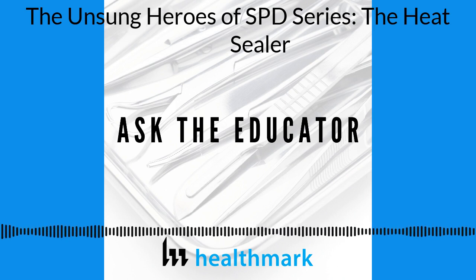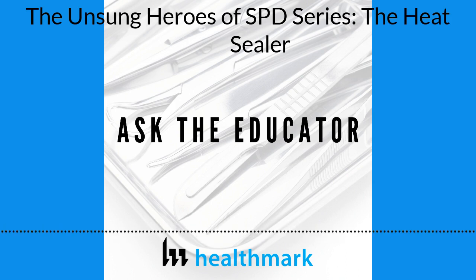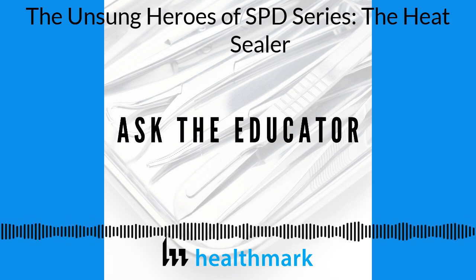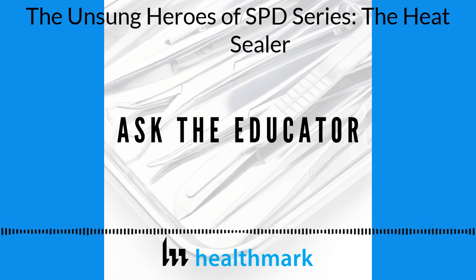Performance qualification, or PQ, of this equipment is supported by numerous standards and documents. So don't wait for the unlikely scenario of a surveyor to ask you about this equipment, or worse, for a problem to arise with your heat sealer. Be proactive and add a PQ test to your heat sealing device as a part of your quality management system.